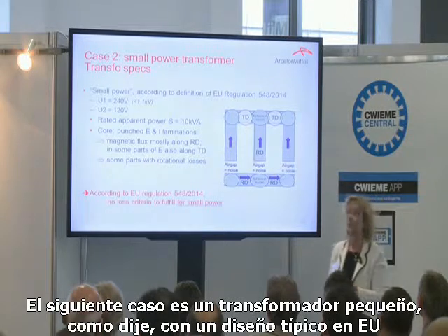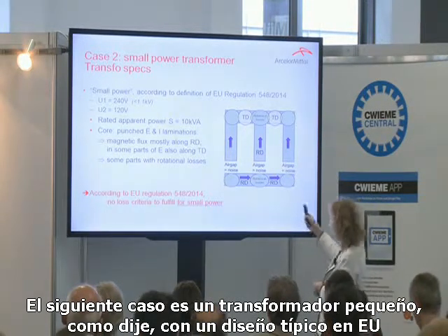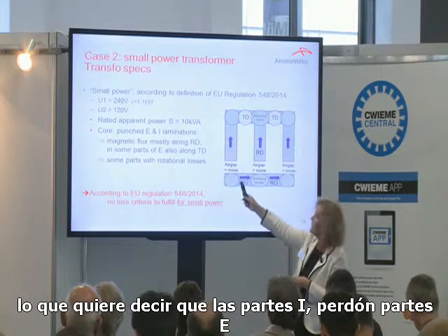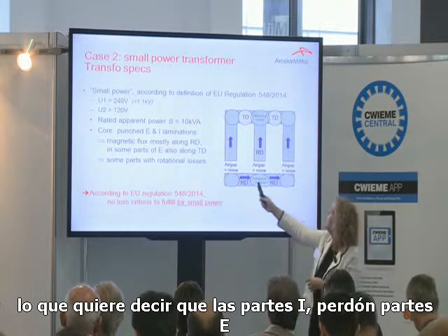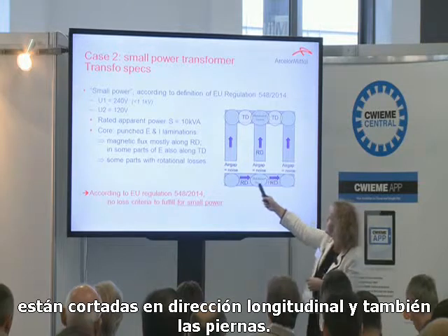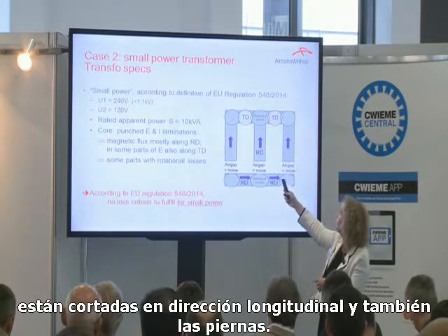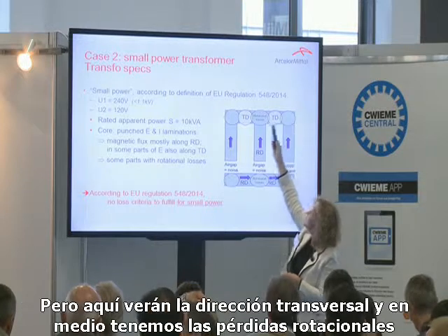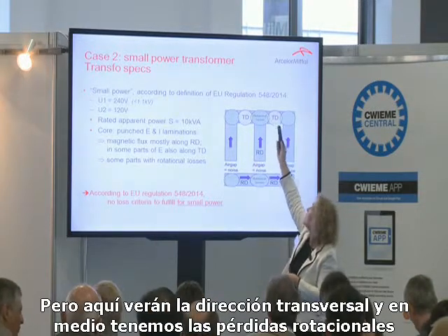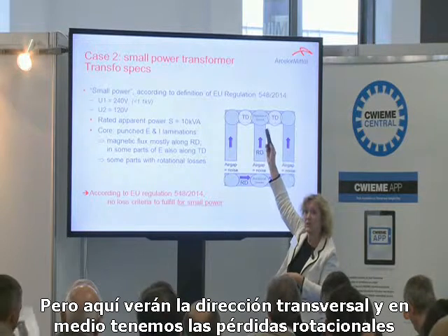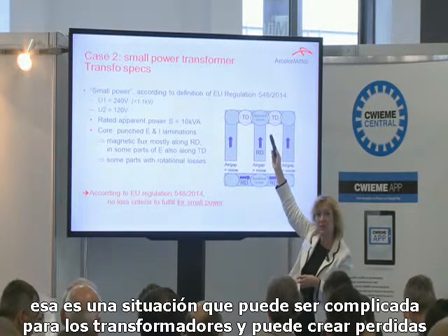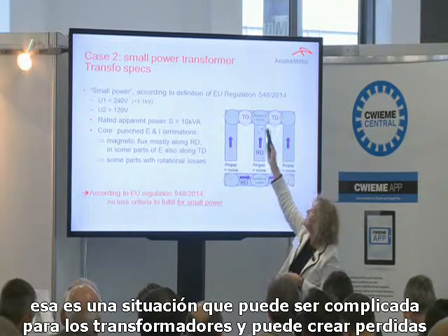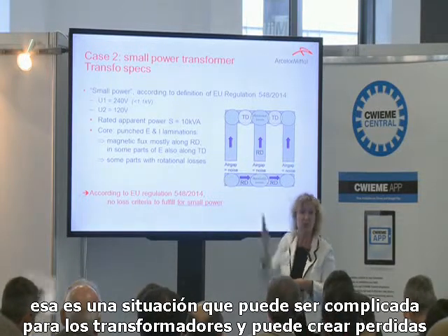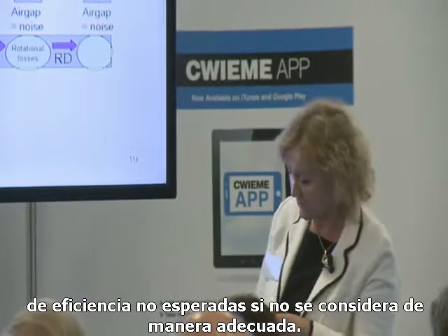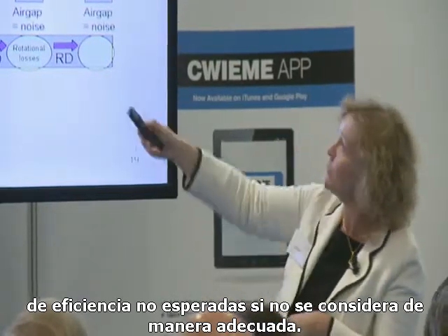The next case is a small transformer, as I said, with a typical EU design, which means that the I part is cut into the longitudinal direction, the rolling direction, also these legs, but here you will see the transverse direction, and in between you will have rotational losses. That is a situation which can be tricky for transformers and can create unexpected efficiency loss if you didn't take it into account properly. So it's a small transformer, 10 kVA.